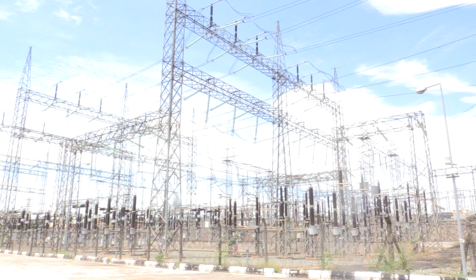What is the coverage of this region in terms of substations and bulk power wheeling capacity? It covers about 6 states. In Anambra, you have Onitsha, which is the main hub, where we have up to 2 or 3 by 150 MVA, and we're still expanding. Each of those 150 MVA is 120 megawatts, so if you have 3, we are talking of 360 megawatts.